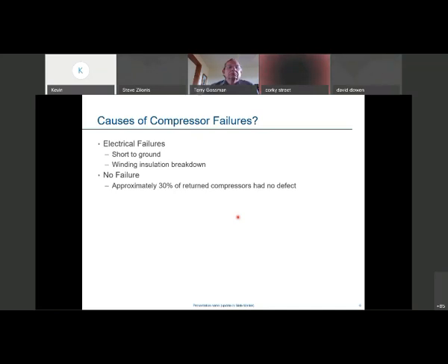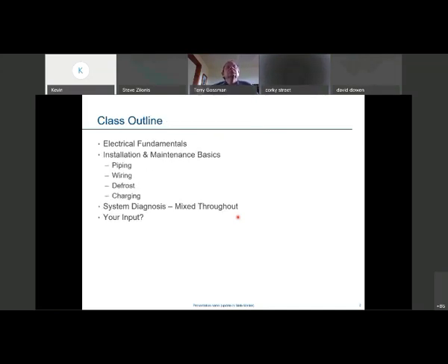No failure at all. About 30% of the compressors that come back to us had no defects, and there's a variety of reasons that could have happened, but that's a very high number, 3 out of 10 that have no problems at all.